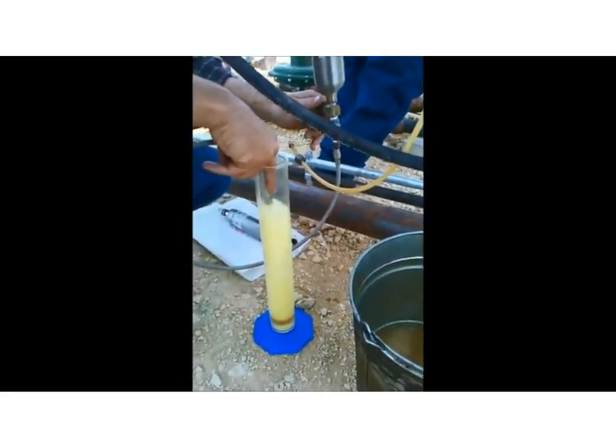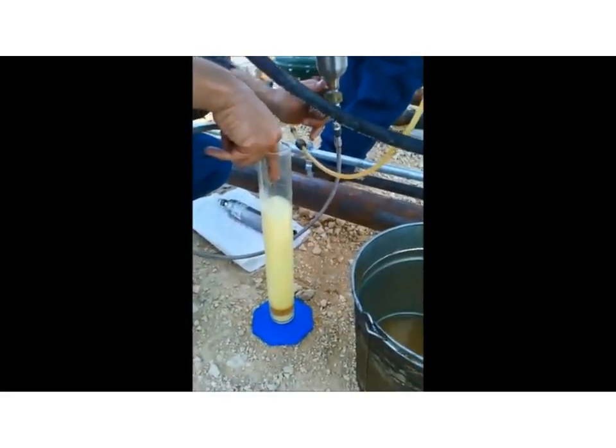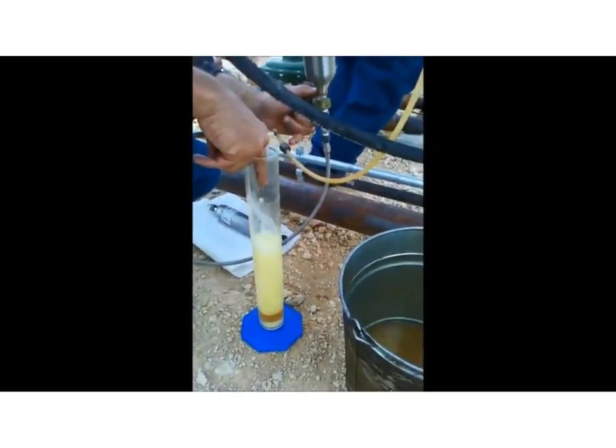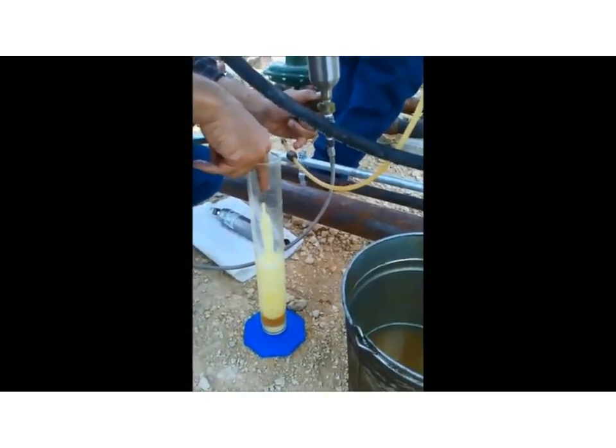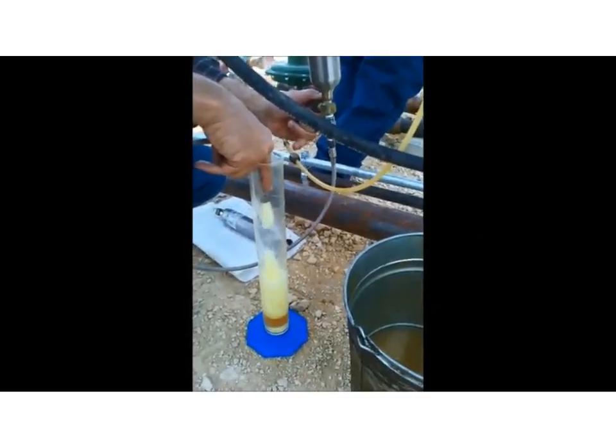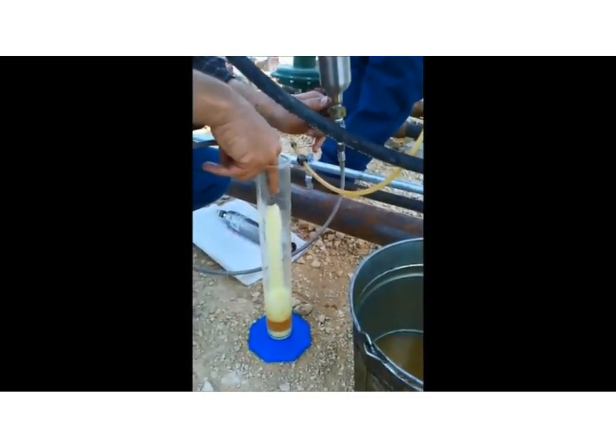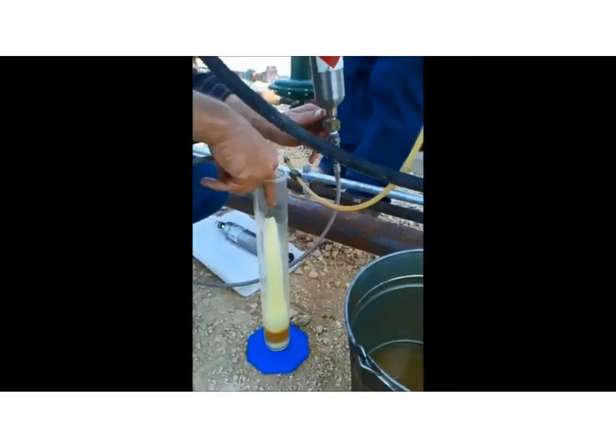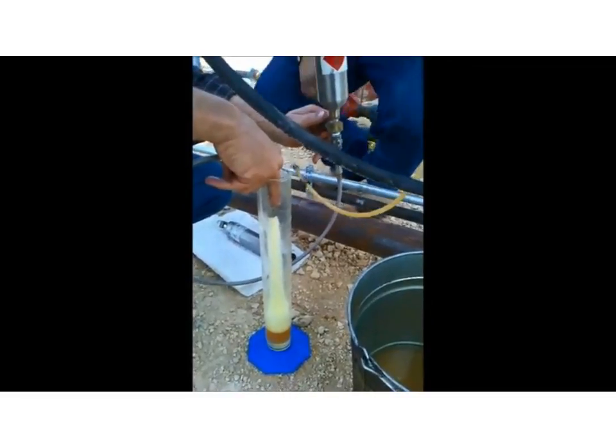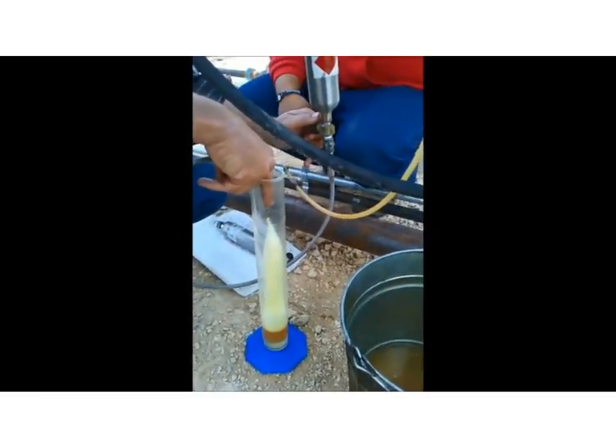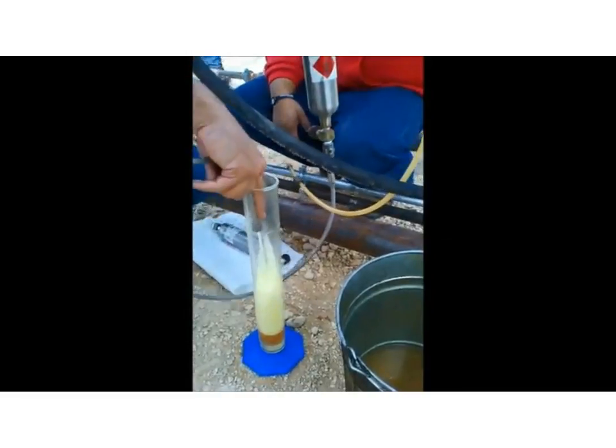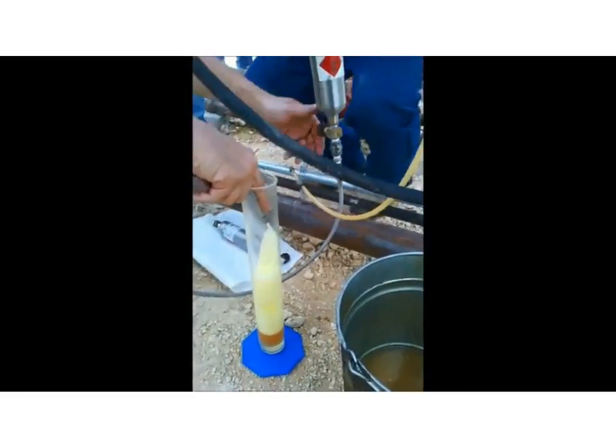hydrocarbon that's being poured out into a cylinder, and because you're changing from process pressure to atmospheric pressure, you're releasing many of those light ends that are contained in these light oils that we're trying to measure. As you can imagine, as you take some sort of pressure drop in your process, you can have that same flashing or foaming occur in your meter, complicating your measurement.